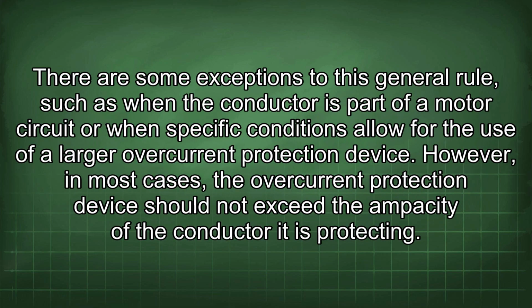There are some exceptions to this general rule, such as when the conductor is part of a motor circuit or when specific conditions allow for the use of a larger overcurrent protection device. However, in most cases, the overcurrent protection device should not exceed the ampacity of the conductor it is protecting.